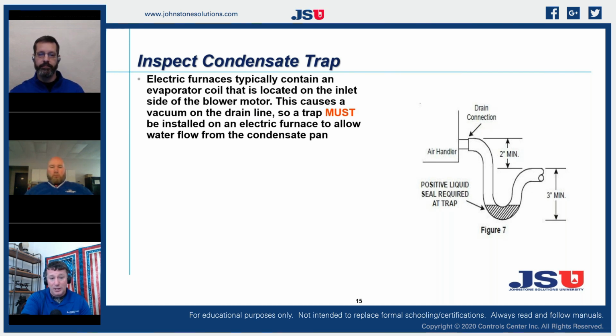So yeah, those running traps will not work, because you've got to think about it, it's all about pressure, right? When we talk about water column, what is water column? If you go back and watch our manometer class and our pressure class, you'll find out that we originally had a 1-inch cylinder of glass that we put water in. And when we hooked a hose from it over to our ductwork, the negative pressure would pull our water up that glass. On the other side, it was doing the opposite, right? So our trap is still that water column. So if I have a 1/2 inch of negative pressure on my blower, that means I can move that water inside of that pipe at least a 1/2 inch up from its standard state.